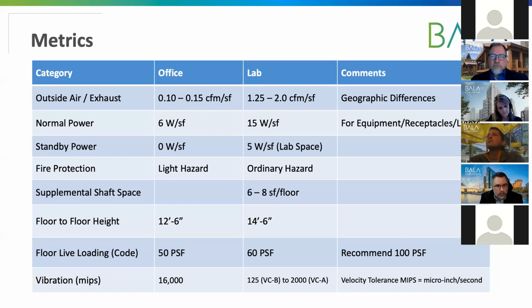Next, we could look at normal power. We see about a 3-fold increase going from office to lab, and this 15 watts per square foot is dedicated to lab bench type work. The HVAC equipment power increase is above and beyond this 15 watts. We might see as high as 20 to 25 watts if you combine everything together.